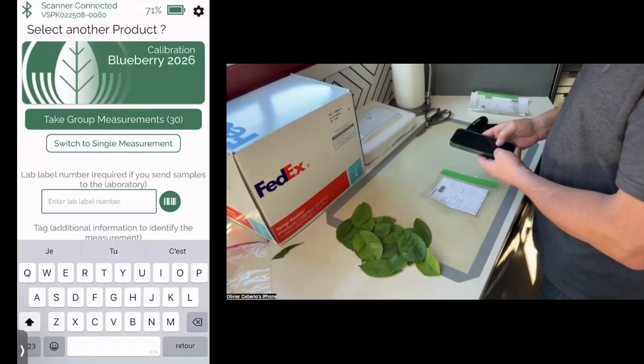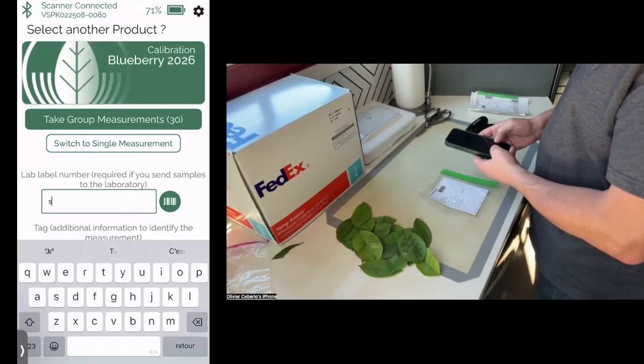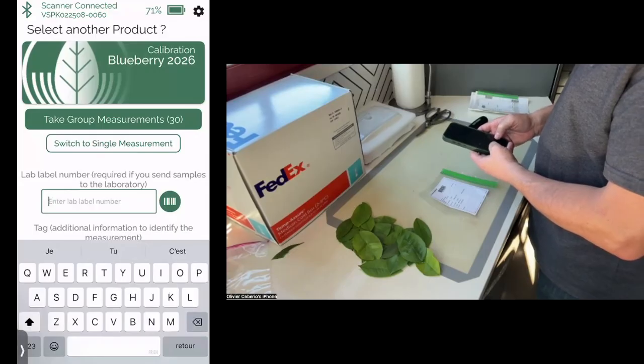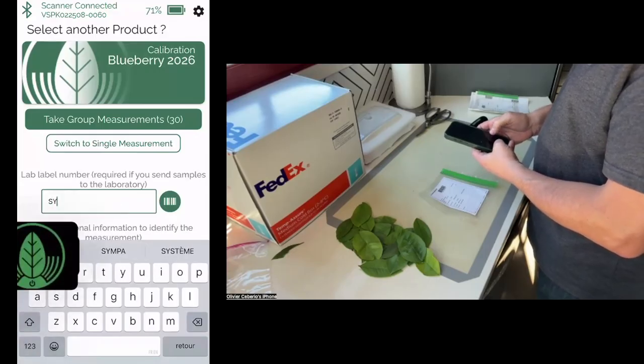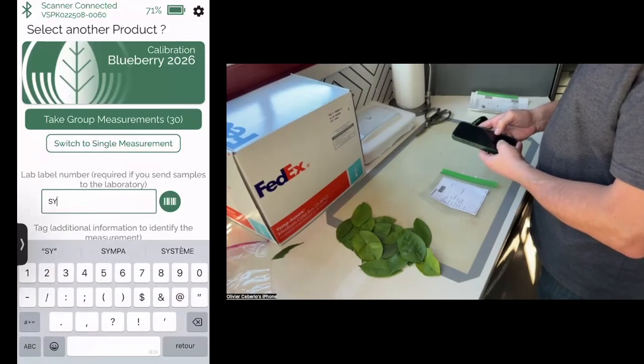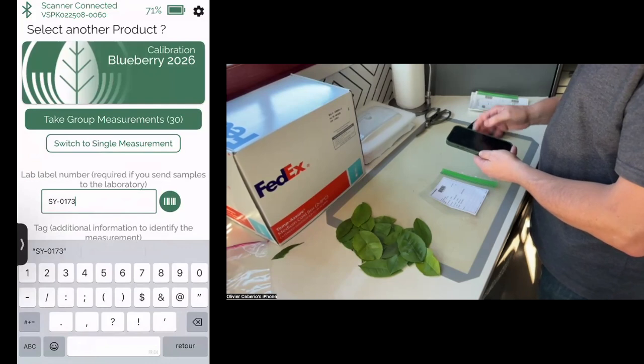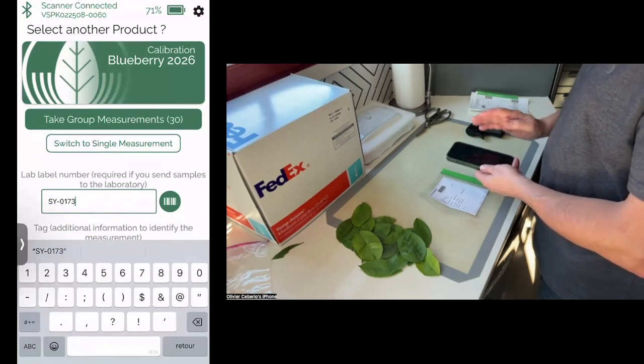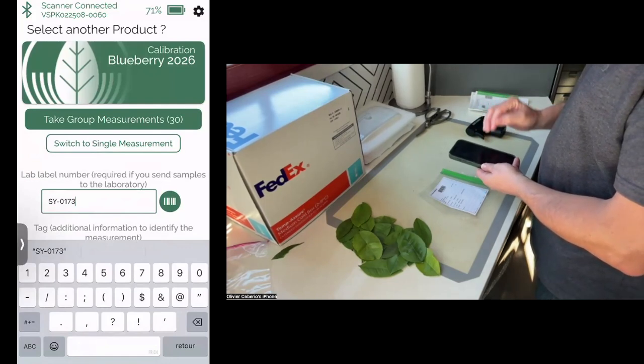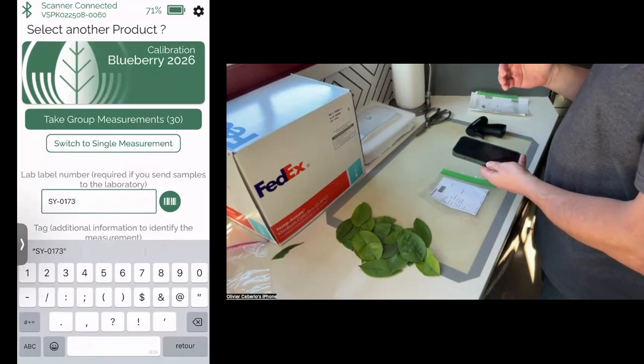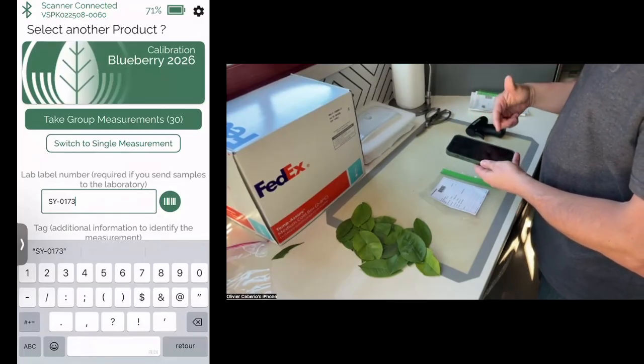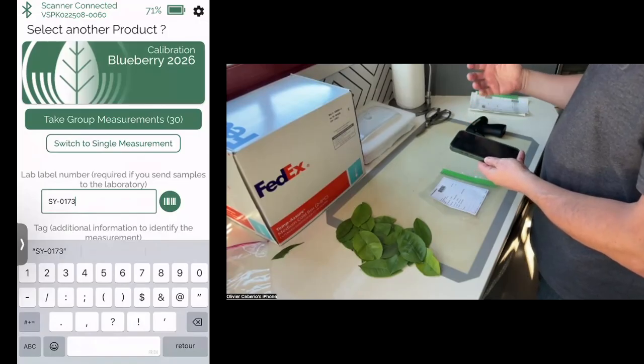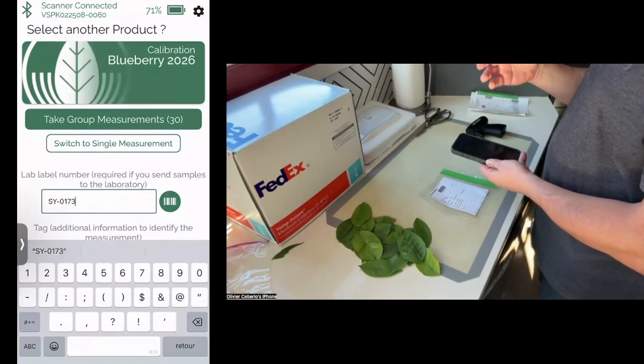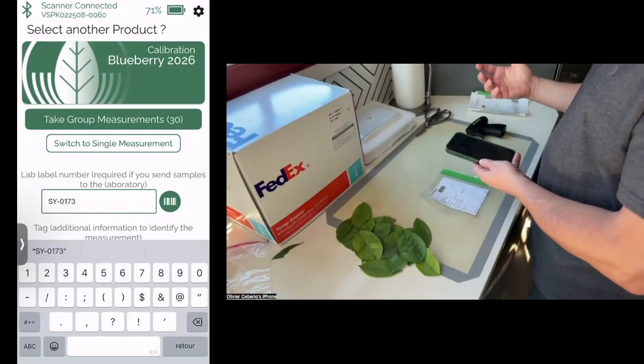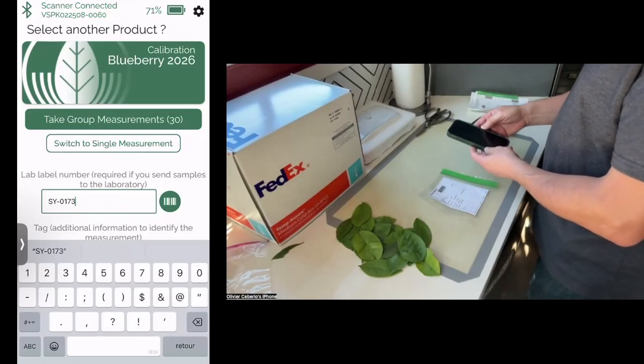So in my case it is S, cap Y, then dash and 0173. And then it's important to check at least twice to make sure that you are not making any mistake here, because this is a critical step of entering the lab ID into the system, so that when we do the calibration, we can actually associate a scan number with a lab number, with a lab result. So then you are ready to scan.